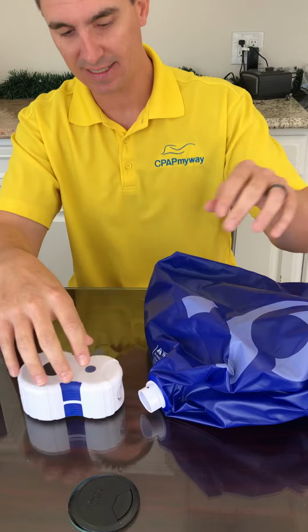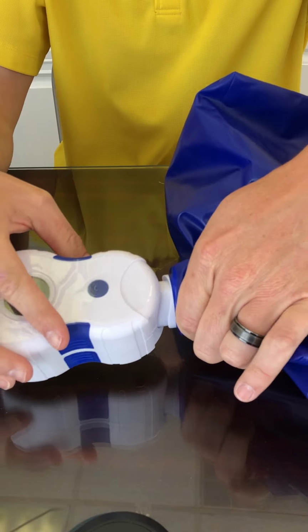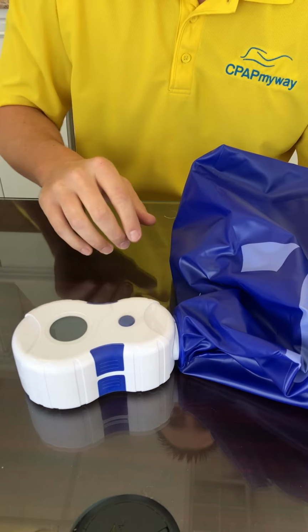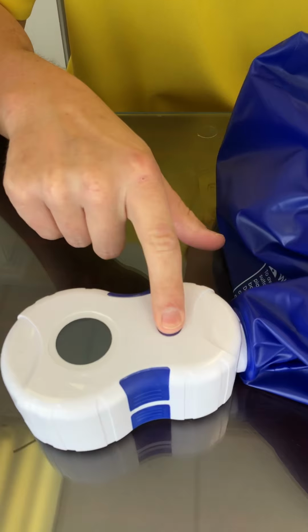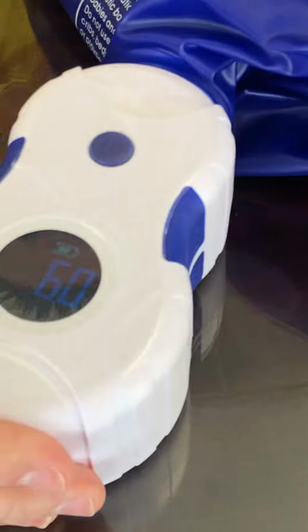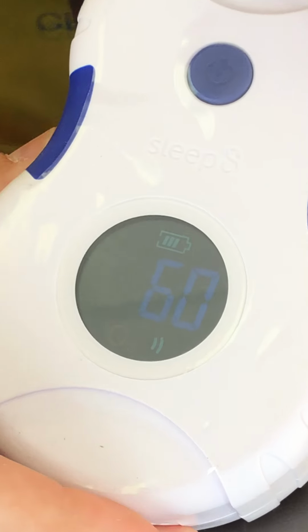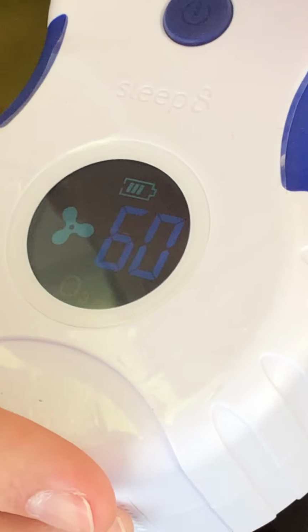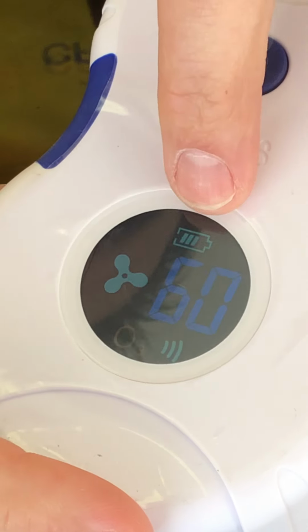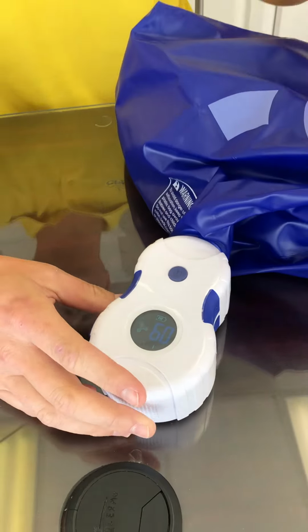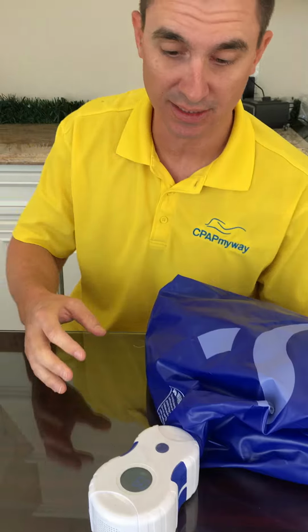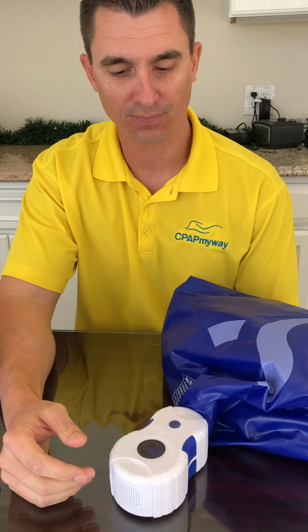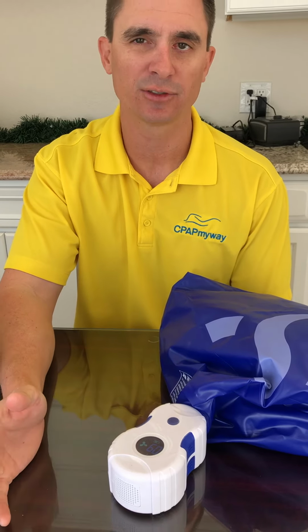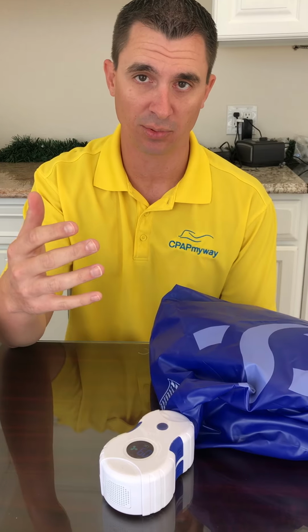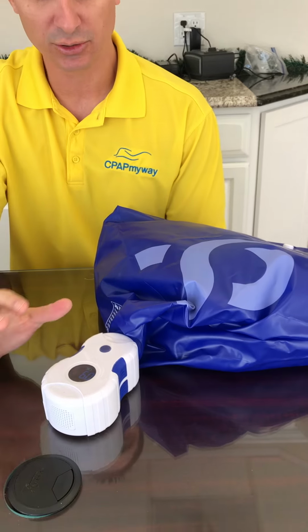So to run the device, the only thing you have to do is match up those 2 little blue dots, connect it on there all the way so that it recognizes that it's connected, and then press the power button until it beeps to turn it on. You notice that when it turns on, hopefully you can see without the glare there, that you get a little fan display running and a number, which is starting off at 60, as well as your battery indicator. That's letting you know that it's running. It'll count down from 60, which is 60 minutes, through the cycle. It needs to run that full 60 minutes to completely sterilize and ventilate the product. So don't try to cut it short.